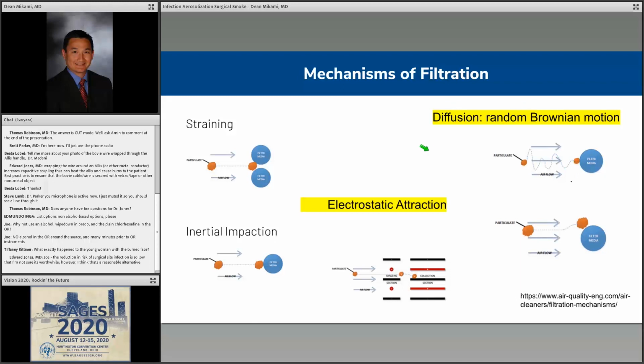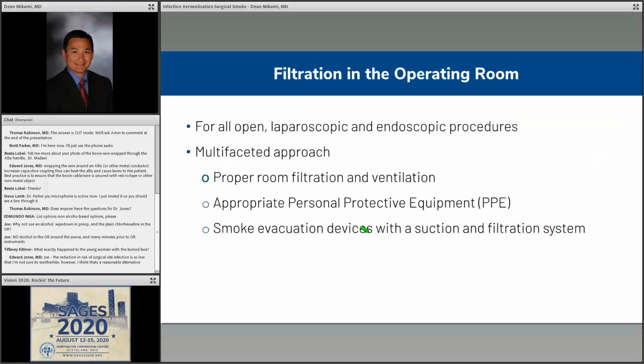Other mechanisms such as diffusion, or actually the particulates can get caught on the filter media and get intercepted, and also get caught that way. And another mechanism is electrostatic attraction. The media fibers of our mask have electrostatic attraction built into it, so particles can get caught through electrostatic attraction. So filtration in the operating room, once again, is very important.